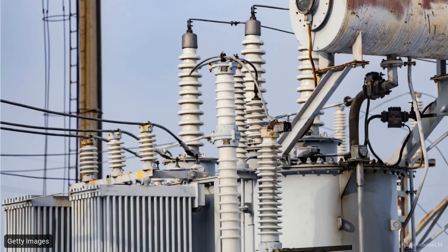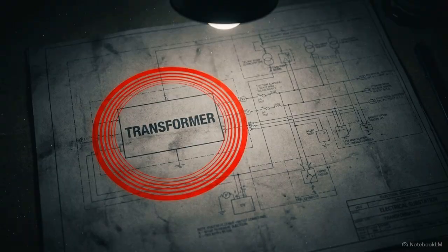How fast that TRV rises is not a constant. The intensity of the race is dictated entirely by the physical layout and specific components of the surrounding power grid. Take a fault physically located near and limited by a transformer or series reactor. This graph shows the resulting recovery voltage. Because of the specific inductance of that local equipment, the fault produces a relatively smooth, exponential, or oscillatory TRV curve.